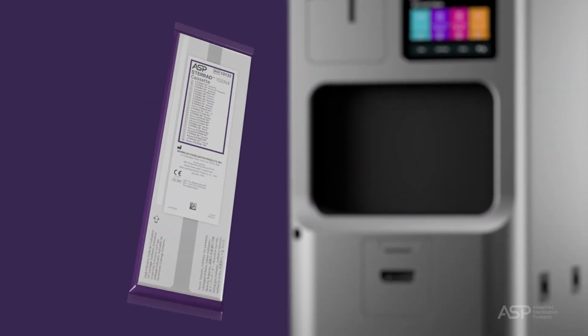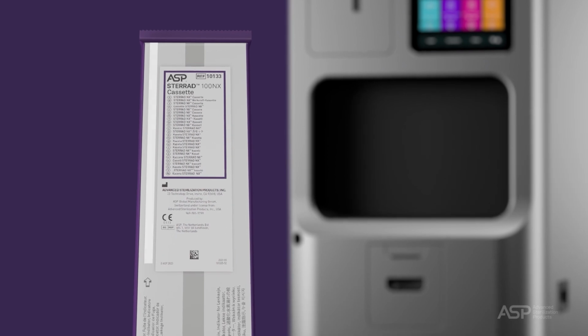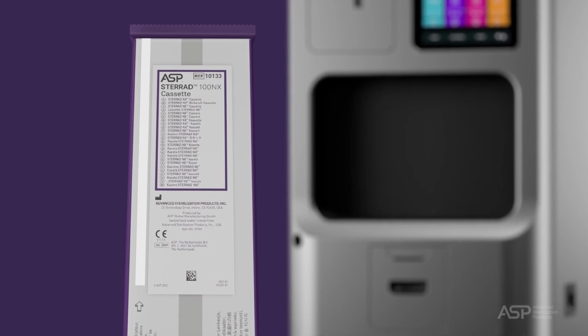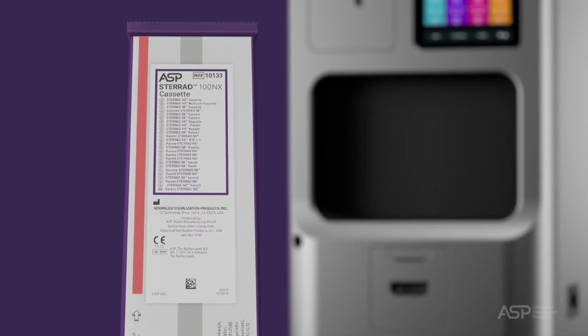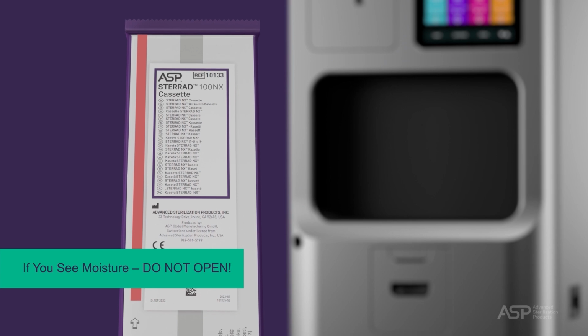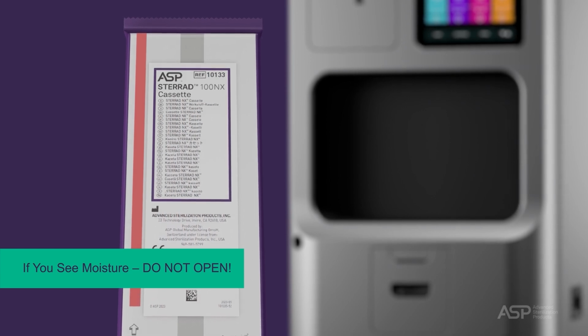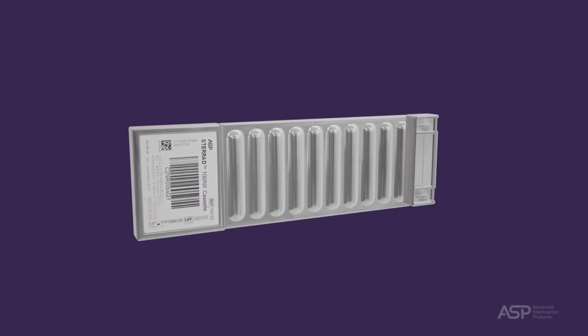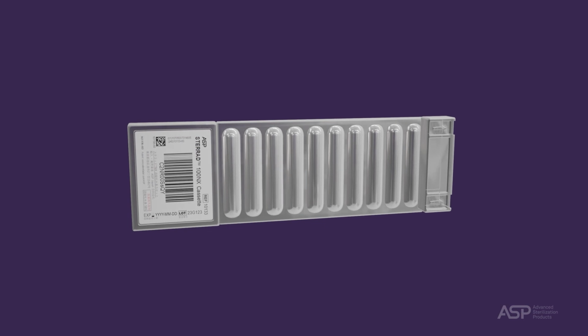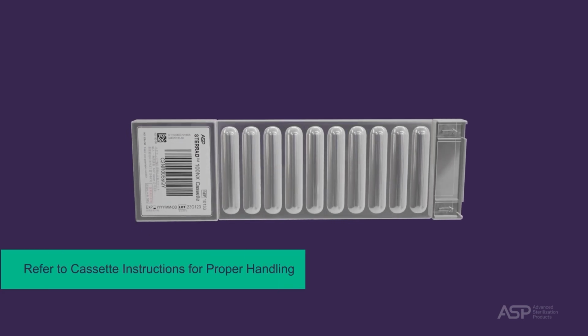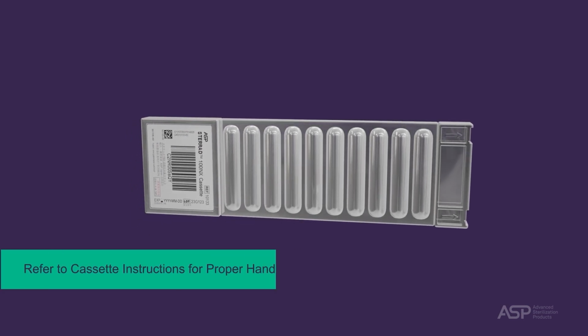Observe the leak indicator strip on the wrapped cassette. If it indicates a leak, the strip changes from white to red. If the strip is red or you see droplets of moisture, do not open the package. It's possible that hydrogen peroxide has leaked inside the package. Refer to the cassette instructions for proper handling instructions.